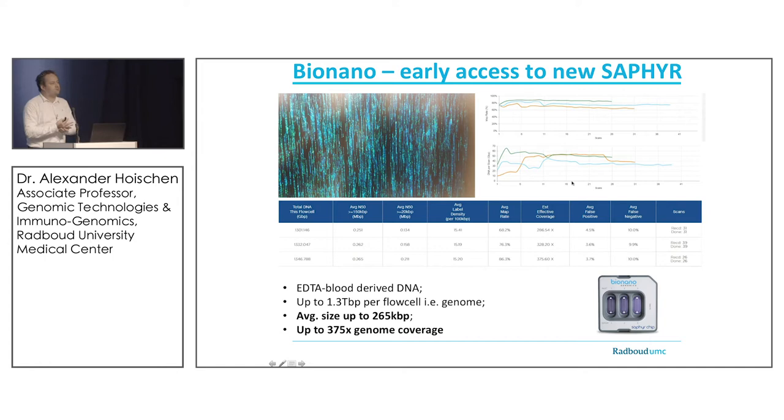This is a screenshot from the very first run we ever performed in-house on the Bionano Saphyr instrument. We generated genome-wide coverage of close to 400-fold, hitting the specs quite exactly on the first run. Samples derived from EDTA blood generated up to 1.3 terabases per sample, with an average molecule size of 265 kilobase pairs. We achieved 375-fold genome coverage — real data from our training run performed at the end of February.